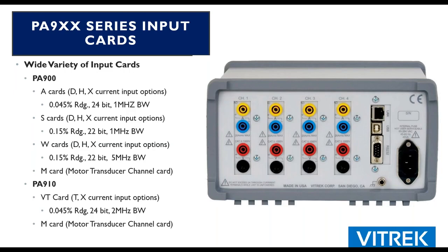Now the next step up in our PA900 series is our PA910. What we did here is, if you look, there are only 2 cards available for this unit. We have the same accuracy, 0.045% of reading at 24-bit resolution, and 2 megahertz, so we bumped up the bandwidth a little bit for that 0.045% accuracy category. We have our VT card, which also has 2 options as far as current goes. The T option is going to get you the ability to go from 0 up to 30 amps. Remember the other card, the A card, went from 0 to 20, and the high current option took you up to 30. Here you're going from 0 to 30 from the get-go. The X is also the external current probe option, and the PA910 also has the M card capability for our motor transducer.